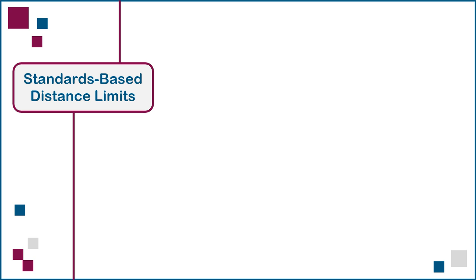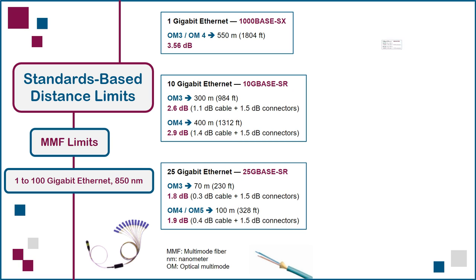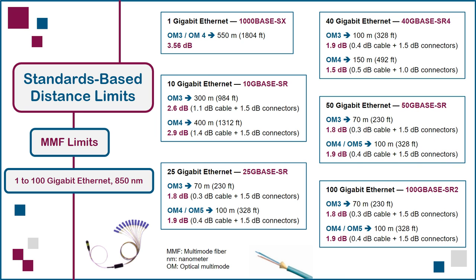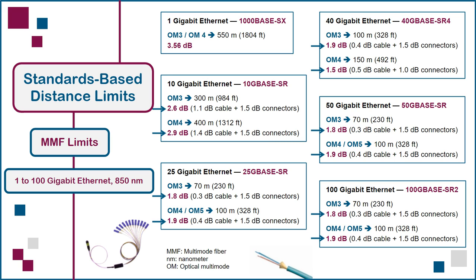Here, we summarize the standards-based end-to-end maximum allowable channel length and end-to-end attenuation or loss values for multi-mode fiber at the 850-nanometer wavelength, for 1 gigabit, 10 gigabit, 25 gigabit, 40 gigabit, 50 gigabit, and 100 gigabit ethernet. Note that the 1, 10, and 40 gigabit ethernet specifications all predate the introduction of the OM5 fiber grade, and in the case of 1 gigabit ethernet, additional testing was performed later to identify its OM3 and OM4 limits. The allowable losses are expanded into two categories: attenuation as the signal travels over the length of the cable, and attenuation caused by the signal passing through connectors or splices in the end-to-end channel. As the data rates increase, both the maximum allowable channel length and attenuation values are reduced, with the OM4 and OM5 fiber types providing a longer reach than OM3.